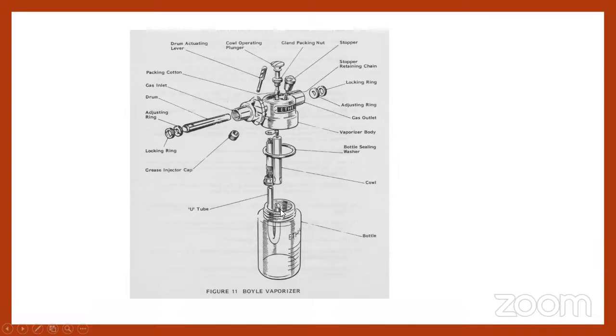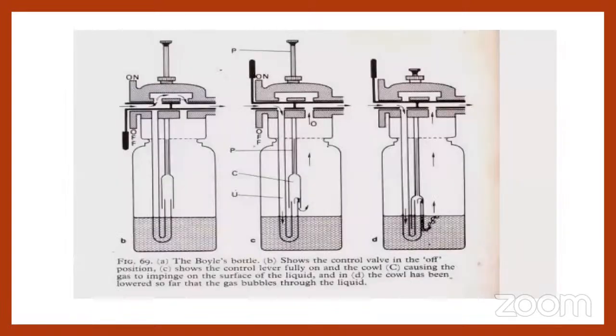So the next image I can show you. Yes. So this is the normal Boyle chamber in the off position. This is the lever, basically a mechanical lever, to make it on or off. Now when it is in the off position, the fresh gas from the left side will enter the chamber, pass through, and go in this direction, and it will go directly to the patient end without mixing with the vaporizer or the anesthetic liquid.